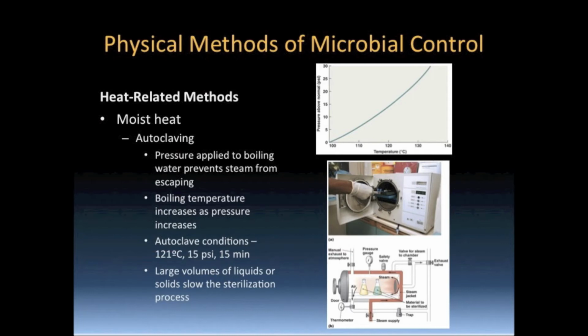Thus, it is important that steam be able to contact all contaminated liquids and surfaces. The time required for sterilization is dependent on the size of the load to be sterilized. The more items within the load, the longer the time required to achieve sterilization.